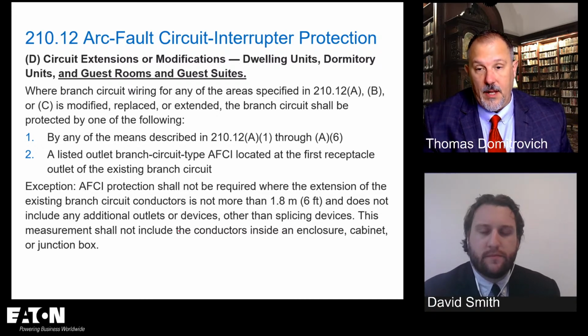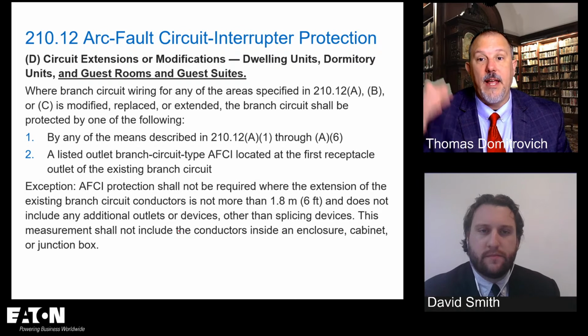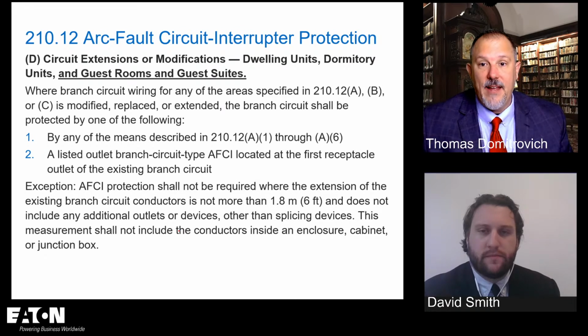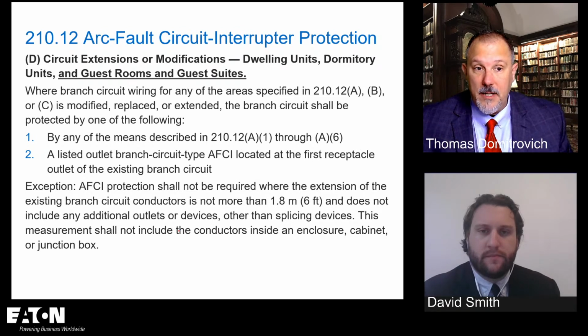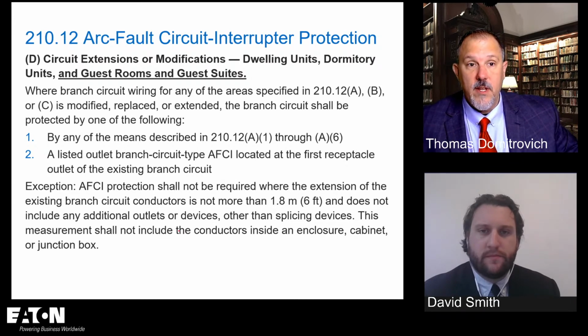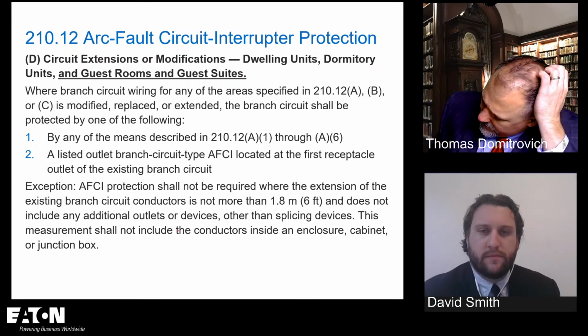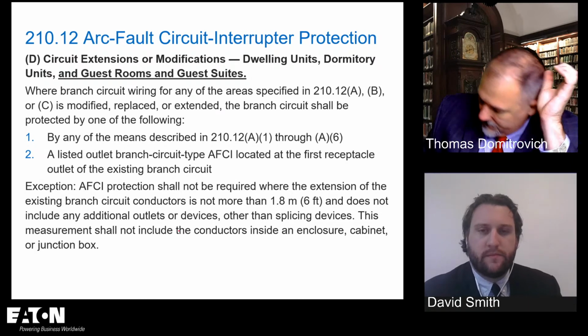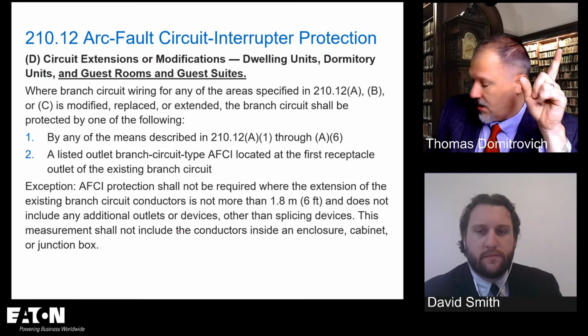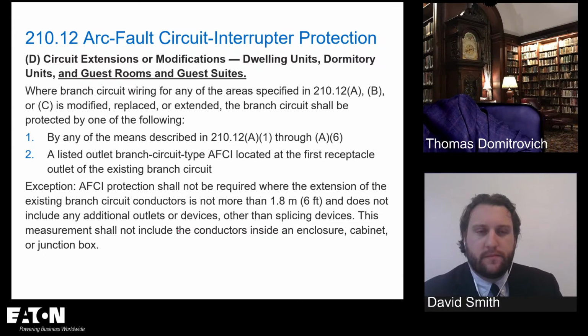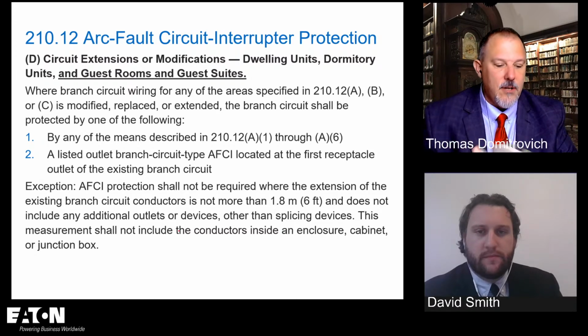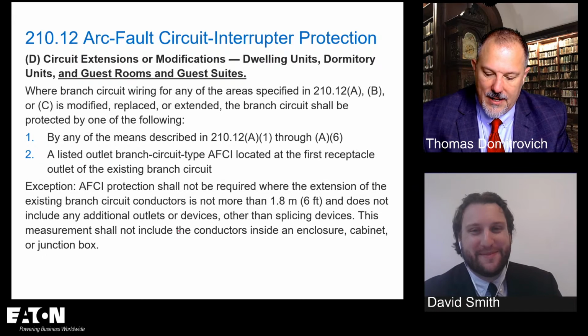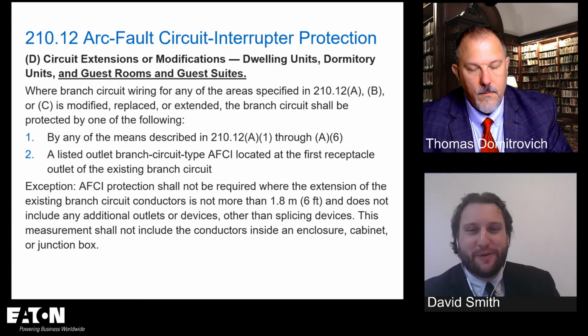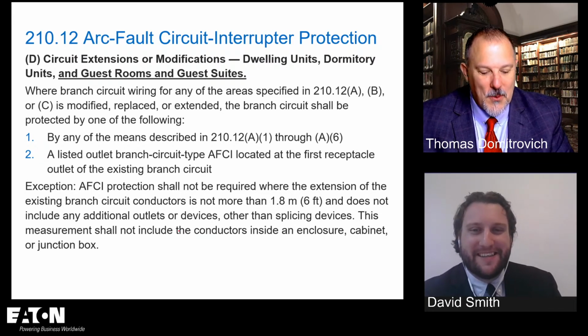They're having people think that every branch circuit now has to be AFCI protected because, I mean, I have knob and tube. Remember when this went in, I'd have to look if the combination AFCI was required. Let me look at the... I'd have to look at the 05 code too. I got the 11 here. He's breaking out the scrolls, the tablets. The scrolls.